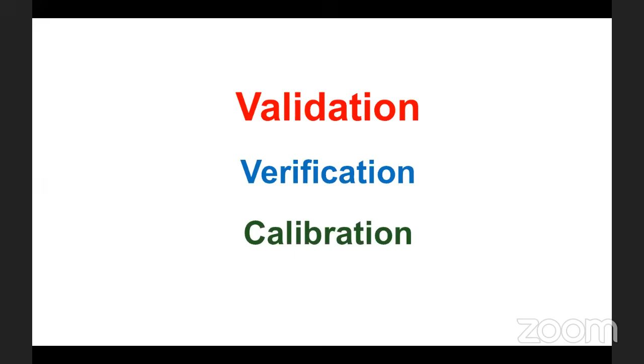And these calibrators shall have traceability to a national or international standard. This is called metrological traceability. This process by which our results are traceable to national and international standards through an unbroken chain of comparison is called metrological traceability. Now, after discussing all these terms, when we are evaluating a particular machine, we have to evaluate. This is important from the company perspective also. If you are installing a particular machine, always check where exactly they are going to put that machine, whether that space is adequate and appropriate for that machine or not.